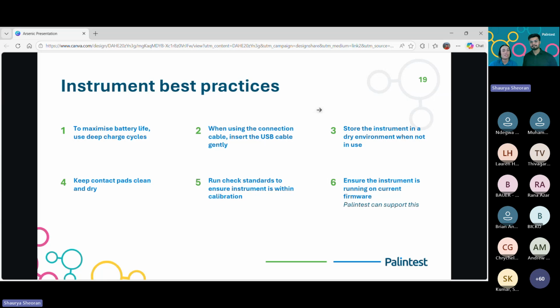And there are a few more in here, for example, inserting the USB cable gently, storing the instrument in a dry environment, keeping those contact pads clean and dry. I know I've mentioned it a few times now, but it is very important to keep that contact pad clean and dry, because if that is working well, then the instrument will give the most accurate results possible.